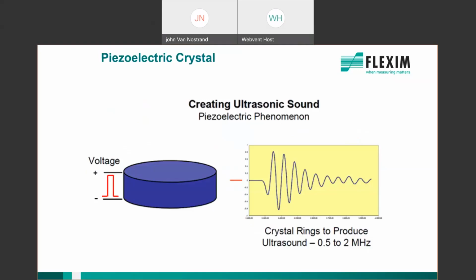The way the meter works is we use a piezoelectric crystal inside the transducer, and we create an ultrasonic wave that rings in the range of about 300 kilohertz to 2 megahertz, depending on the transducer selection. We go much, much lower for tough applications like precast cement pipe. One thing worth noting is that FLEXIM uses a propagation voltage of 40 volts, which is about twice our competitor. So we get a very strong signal and a very clean signal through the pipe.